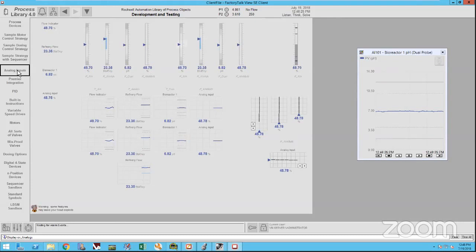As soon as this releases in about a week or two, you'll be able to download this new set. Like I said, the only requirement is that you're going to need to have FactoryTalk View SE version 10. But from a controller side, we can go all the way down to 24. I think we can go down further than that, but realistically, we'd probably be on 24. But for the full PlantPAx system release that we're looking at: FactoryTalk View version 10, Studio 5000 version 31, FactoryTalk Asset Center version 8, Historian will be version 5 or 6, and Vantage Point will be version 8.